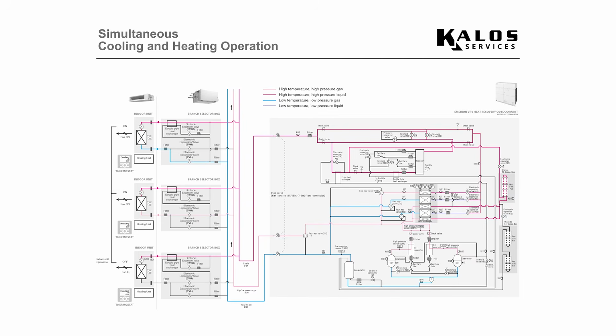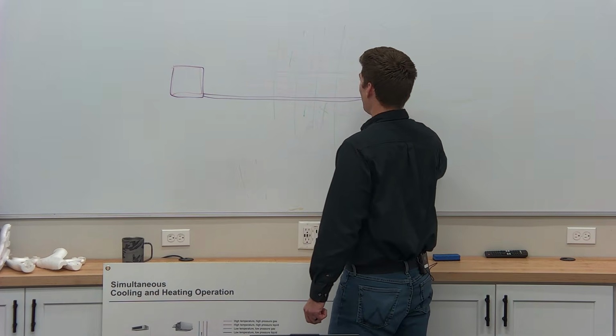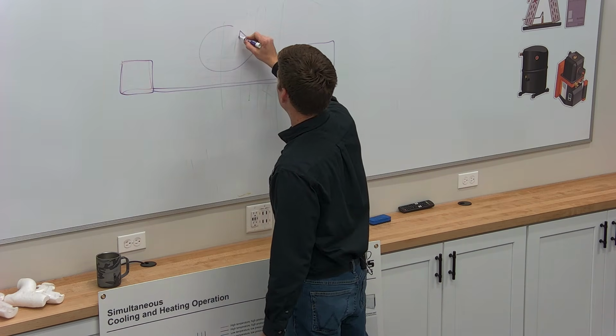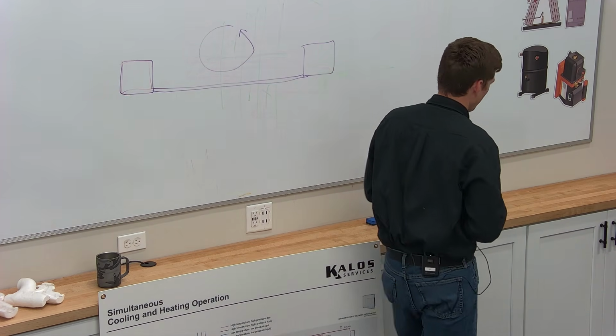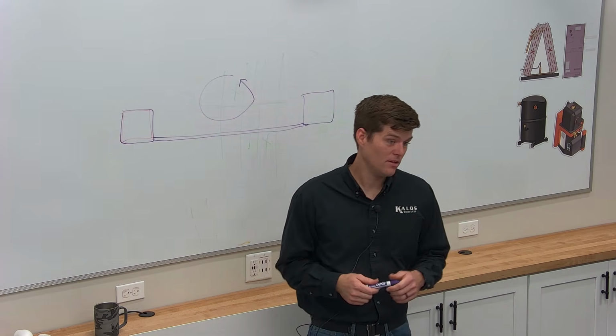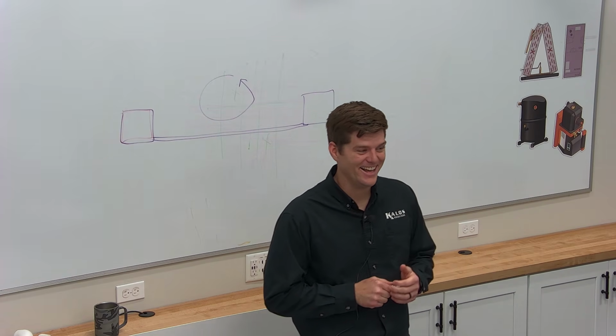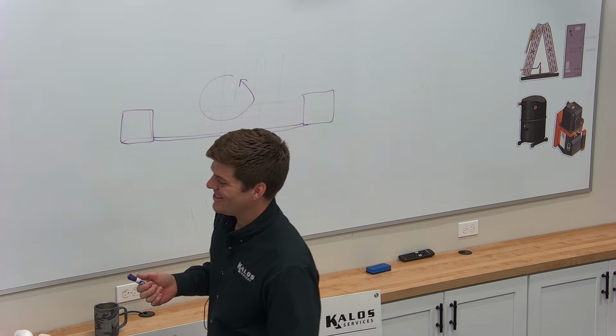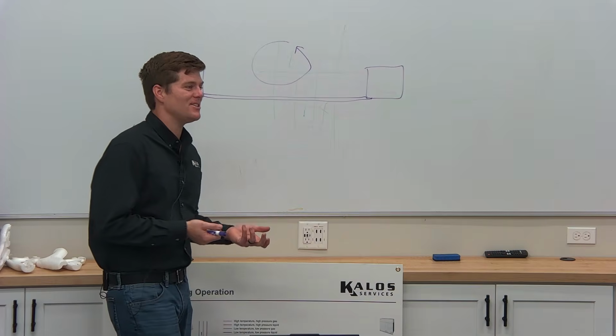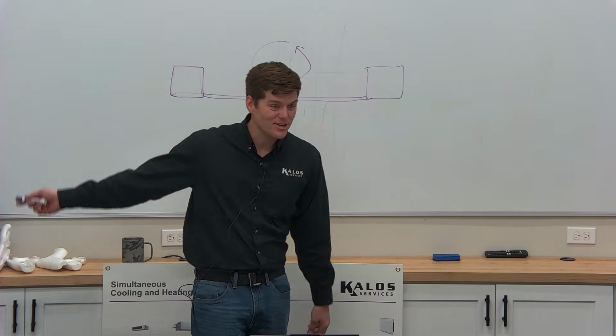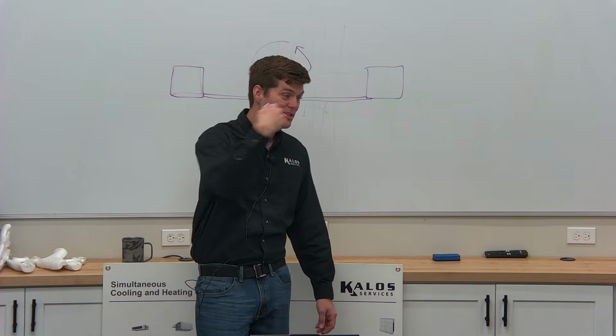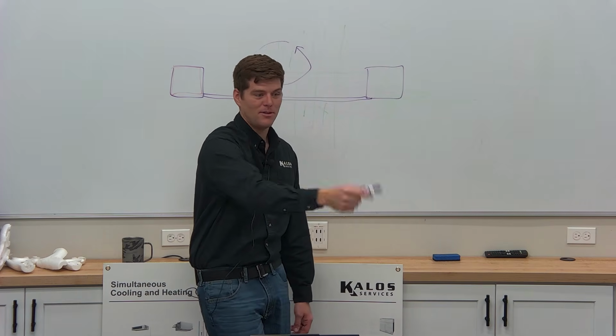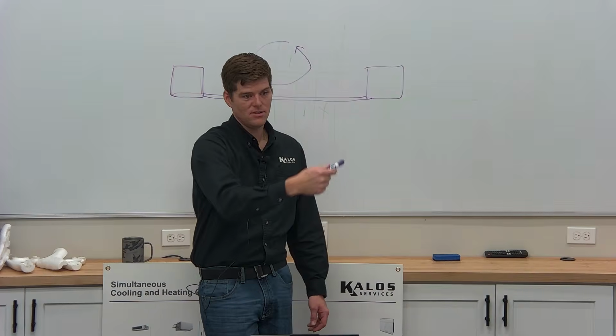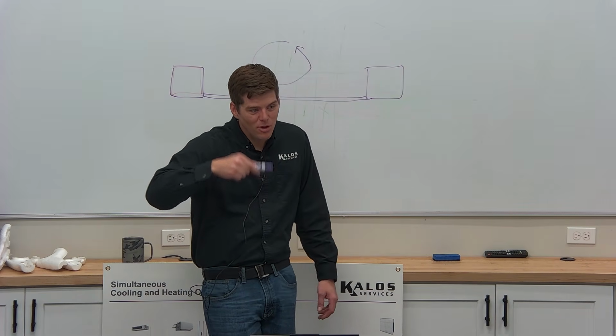So when you have a large system like this that's operating the way that it does, something that comes to my mind frequently, and that's only because I've been troubleshooting it for so long, when you have one indoor unit and one outdoor unit on a split system, and the refrigerant is doing this, right? What's one thing we don't usually typically worry about? Explosions. Well, yeah. Give it a couple years. Oil. When I've got a split system, like the one behind you there, and my outdoor unit is only 50 feet away, and it's just a standard loop. It's either going this way or it's going this way as a heat pump. That's one thing I don't worry about. Oil. It's a short distance. It's only doing this in a small revolution. Where's it going to go?